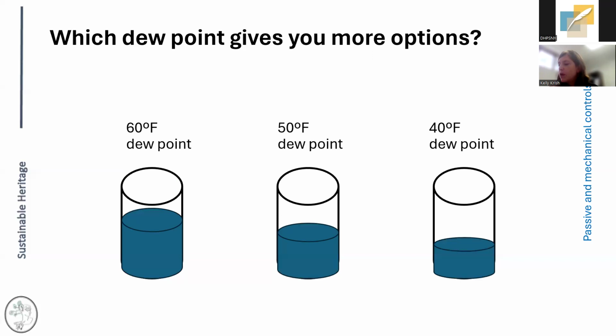Okay. With this, I wanted to build off of that as well, just to drive home the point: if you think about a 60-degree dew point, how much moisture that means is in that container. You can only lower the temperature and shrink that container so much before you're going to hit a relative humidity that's too high for collections, and be looking to condense out. Whereas at a 40-degree dew point, we can shrink that container quite a bit more before we're at risk for too high relative humidity. So hopefully that makes sense, but it's just to say we have more options for temperature and RH control at lower dew points, but with our mechanical systems, it's often a locked-in option.